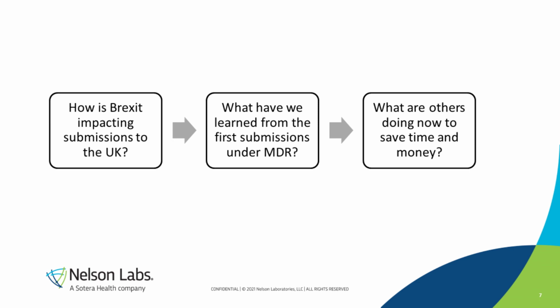And how we look at saving money for all of this is actually using the right education and experience on biocompatibility assessments to determine what testing is even necessary. So when you're looking at the testing evaluations that we talked about before, the secret to this whole concept, even though it sounds like it's so much harder, so much more onerous on you as a medical device manufacturer, you've got to remember that if you do this correctly and you gather the right information up front and even do the chemistry, we're able to evaluate a lot of those biological endpoints from a risk-based approach, which means you're not spending the 16 to 19 weeks it takes to do an implantation test. We may not have to do an implantation test, depending on the material information you gather.